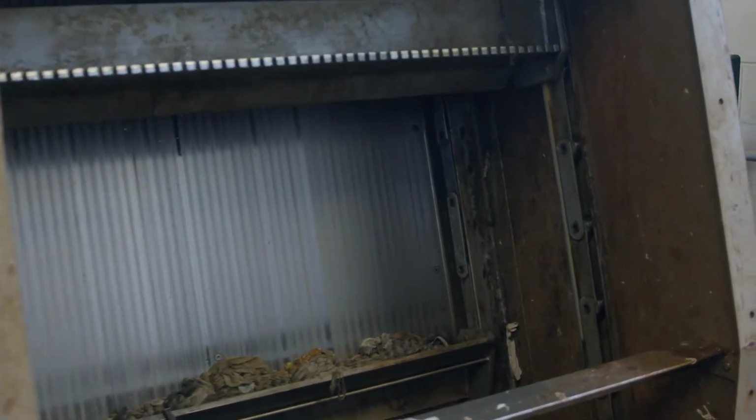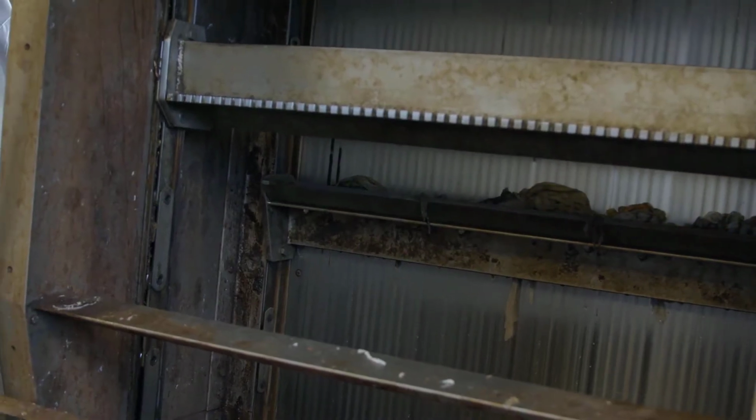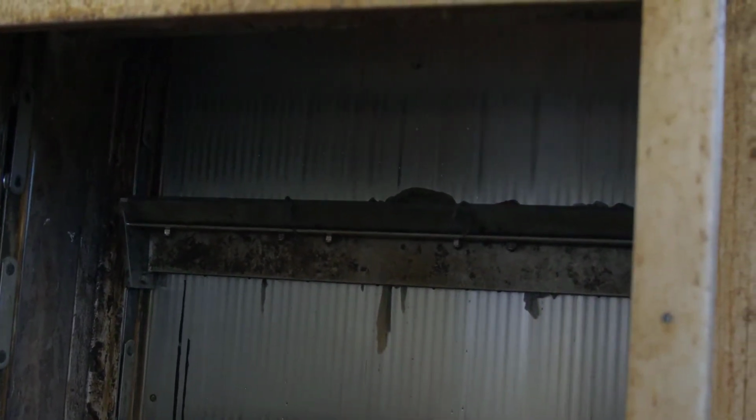A bar screen is typically the first level of physical removal used by a wastewater treatment plant for incoming wastewater, or influent. The bar screen is designed to remove objects such as wipes, rags, and plastics from the influent and protect the pumps from clogging. Some bar screens are old and may be rusted or degraded and otherwise compromised. When you visit a plant, check to see if the bar screen is in good working condition or if certain trash may be getting through.